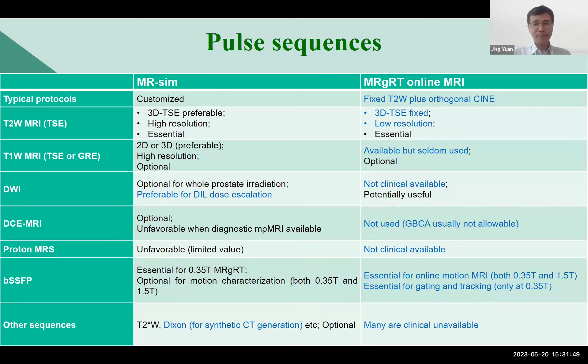currently on the Unity system, it is still a research sequence under development. And T1-weighted MRI, on the other hand, is an optional scan sequence because it has limited value in tissue delineation. In online MRI, DCE MRI is usually not allowed. And as I mentioned just then, the bSSFP sequence is a gradient echo sequence. It is used in MRGRT for real-time motion monitoring and as imaging reference for the gating during the beam-on time. And please note that the comparison in this table is only valid for prostate MRI, so it cannot be directly translated to other organs. As I mentioned, the MRI sequence selection and optimization are much application dependent.